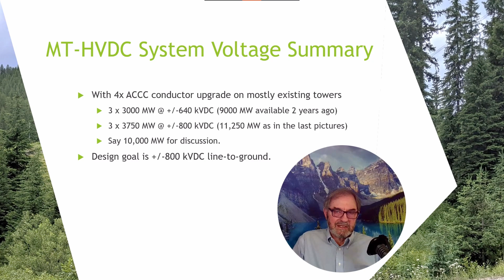Here's a summary of HVDC VSC system voltage figures. With a 4 ACCC conductor upgrade on most of the existing towers, we could get three 3,000 megawatt systems based on technology available 2 years ago. With three 800 kV systems, we could go up to 3,750 megawatts, consistent with the systems shown in the last pictures. Say 10,000 megawatts for discussion.